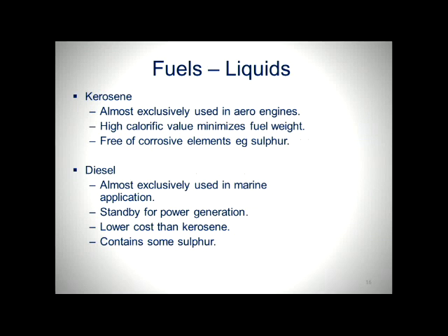Diesel is used exclusively in marine applications usually, or standby for power generation, or offshore, they might use diesel for standby. It costs less than kerosene, but it does contain some sulfur. So you can get damage to turbine blades, especially if the temperature's within a certain range, which I can't remember now, you get hot gas corrosion, and it's caused by impurities in the fuel.